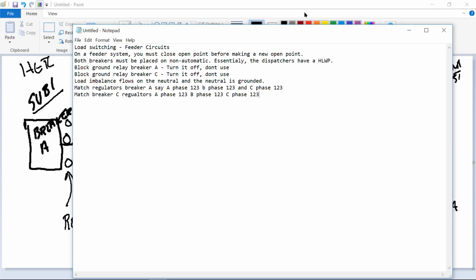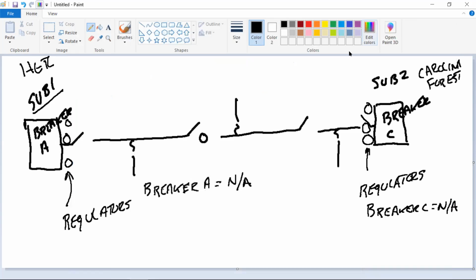If you don't have the regulators matched at either substation and you close the switch, this is going to be catastrophic. One is going to go into what they call reverse power flow. If my voltage is higher here and my amperage is lower, and my voltage is lower here and my amperage is higher, this substation will say, well, my voltage is higher, I'm going to go ahead and try to feed through here. I'm going to try to compensate for the entire circuit instead of sharing it with the other one.